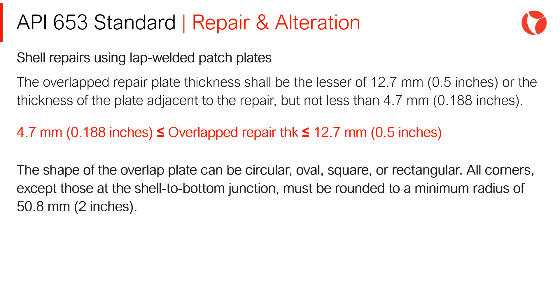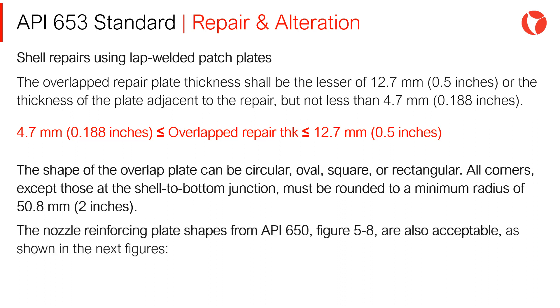The shape of the overlap plate can be circular, oval, square, or rectangular. All corners, except those at the shell-to-bottom junction, must be rounded to a minimum radius of 50.8 mm. The nozzle reinforcing plate shapes from API 650 figure 5.8 are also acceptable, as shown in the next figures.